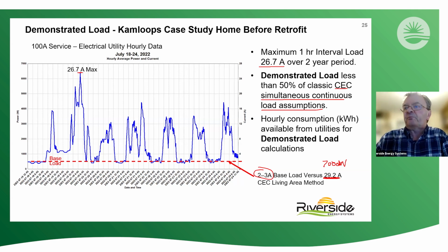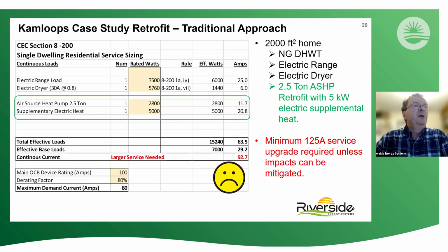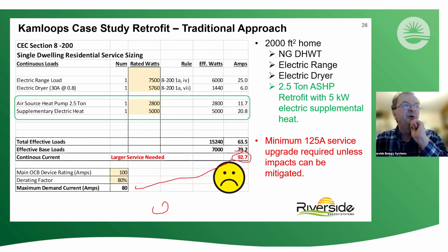So if I go back to this case study house of mine, if I'd wanted to add a heat pump, a 2.5 ton heat pump with a 5 kilowatt supplementary electric boost heater, using the traditional CEC methods, I'd be way over the 80 amps I'm allowed, and I would have had to do a service upgrade. Sometimes we're finding that in retrofits, often this is where things stop and no one digs any deeper.